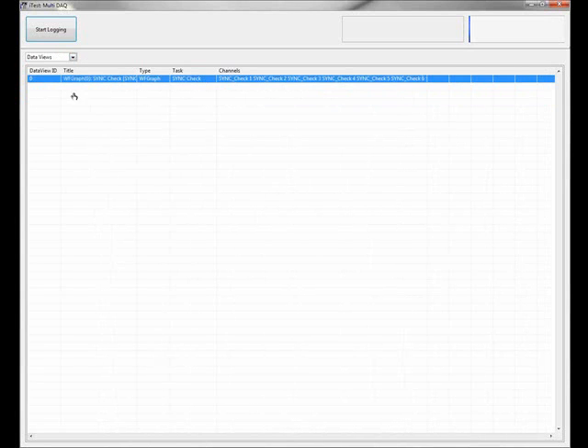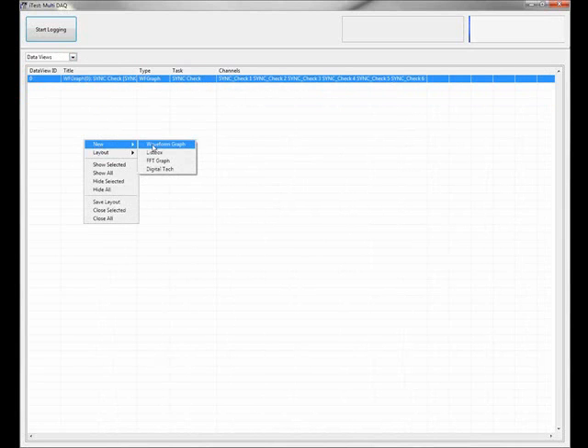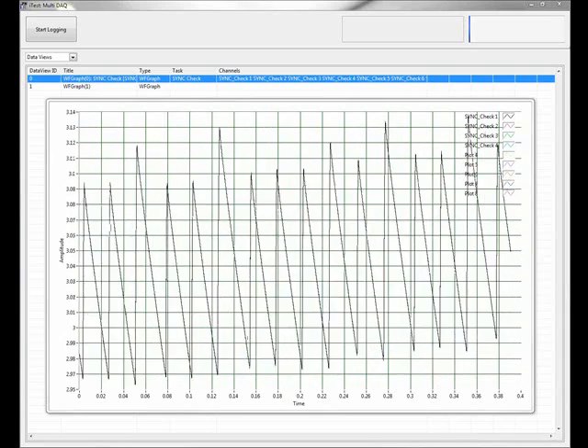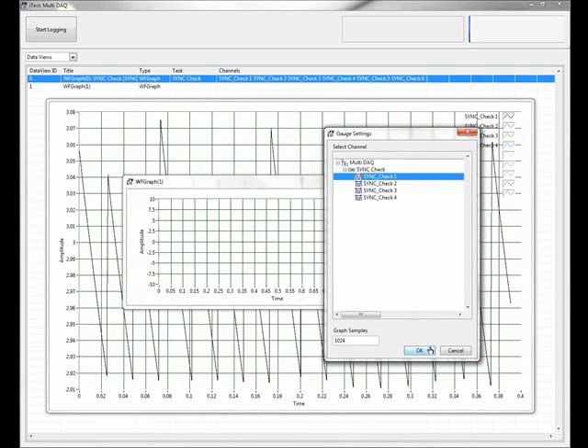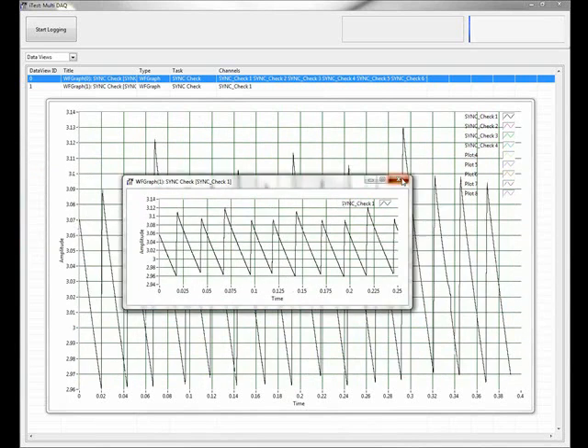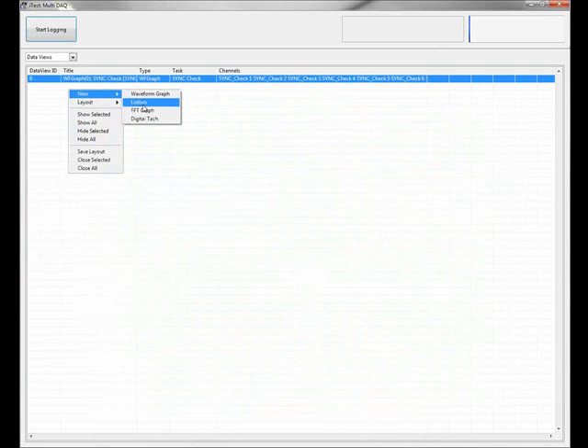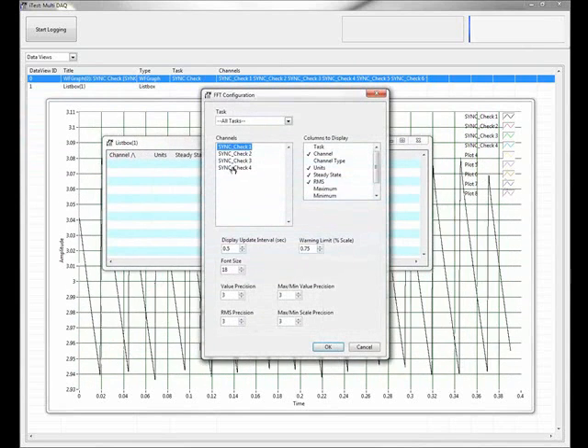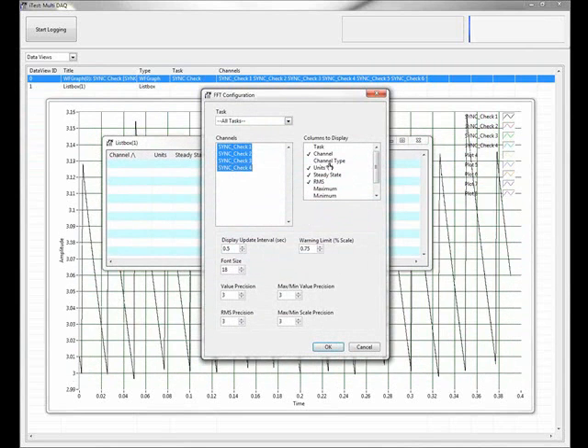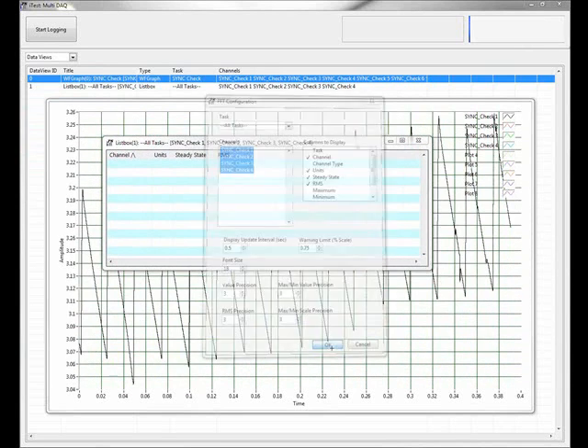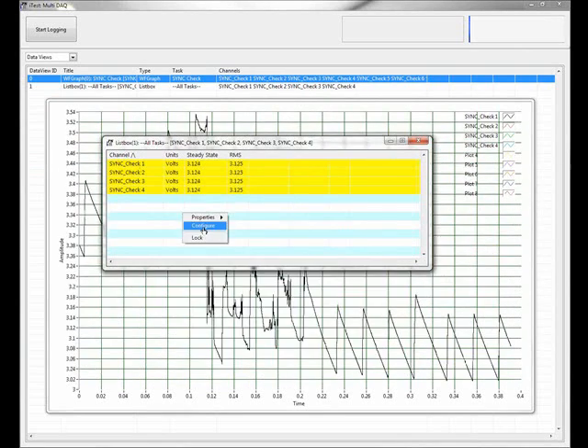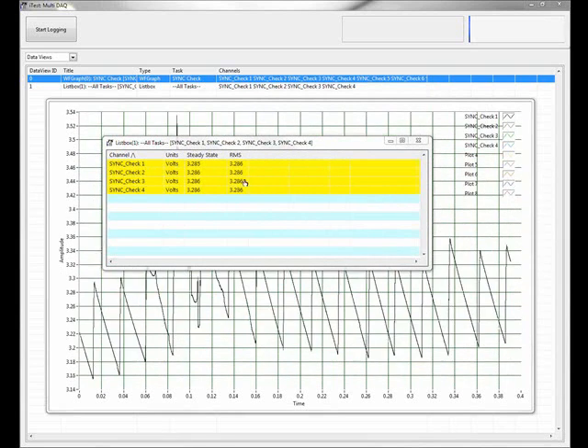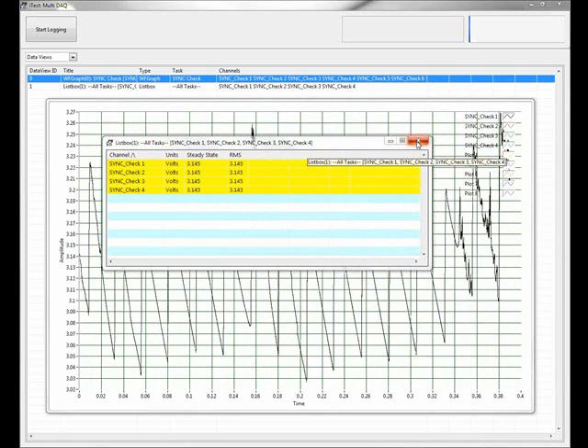Right now I've got one set up. The way I set my waveform graph up is I right-clicked and clicked New, and created a new waveform — you can see it opens up a window. Click a channel to view and set the amount of samples for the graph, and it's going to show you a real-time plot. There are a few others you can choose from by right-clicking in the window. You can do a list box, which is basically a similar digital readout — right-click again to configure, select the channels you want, view the appropriate properties, and set precision for those values. In our configuration, a warning limit is set to about 75% of the max or min value, which is why it's highlighted yellow. If it exceeds the max and min value set, it will turn red.